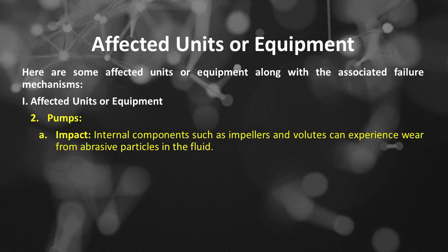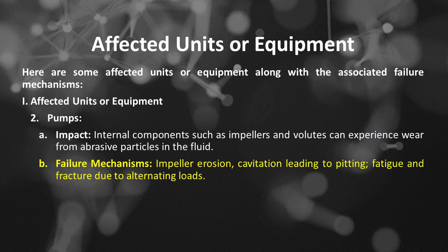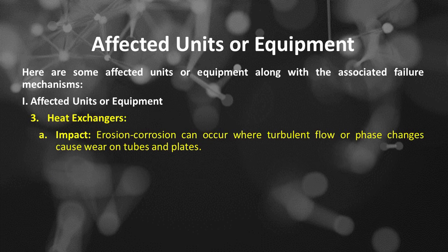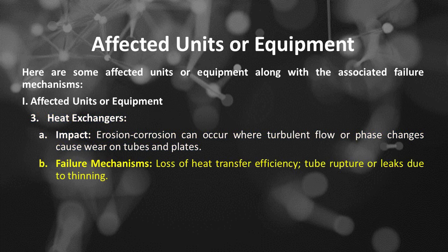Number 2 of the affected units or equipment is pumps. The first is impact: internal components such as impellers and volutes can experience wear from abrasive particles in the fluid. The second is failure mechanisms: impeller erosion, cavitation leading to pitting, and fatigue and fracture due to alternating loads. Number 3 is heat exchangers. The first is impact: erosion-corrosion can occur where turbulent flow or phase changes cause wear on tubes and plates. The second is failure mechanisms: loss of heat transfer efficiency, and tube rupture or leaks due to thinning.